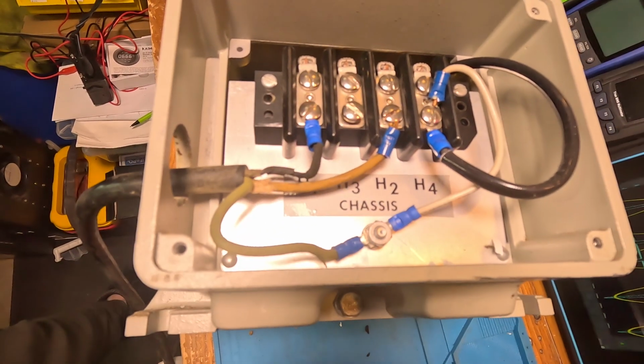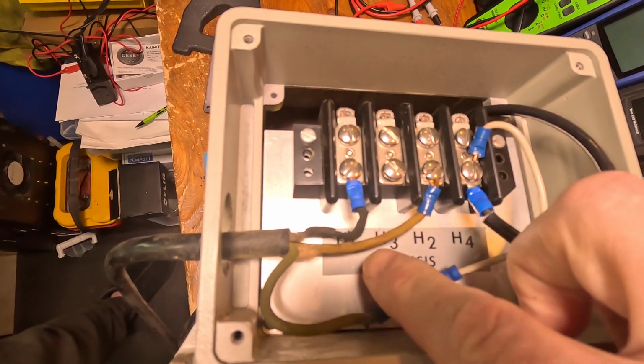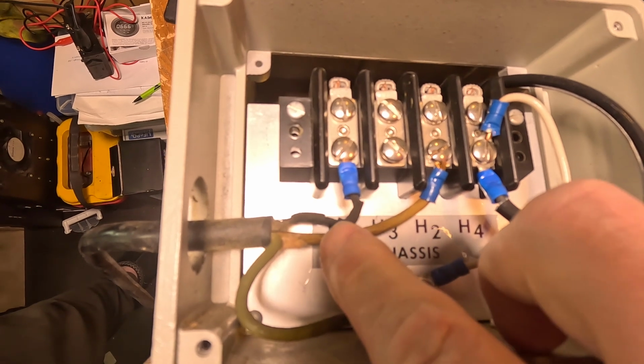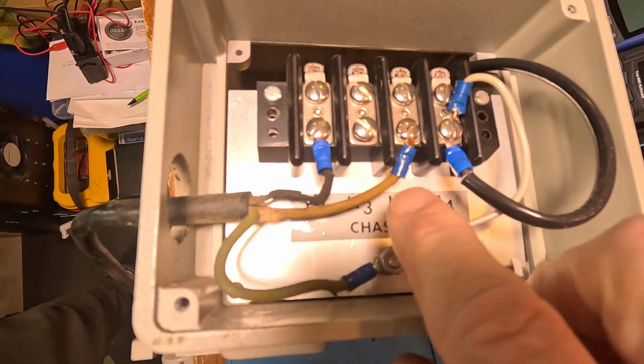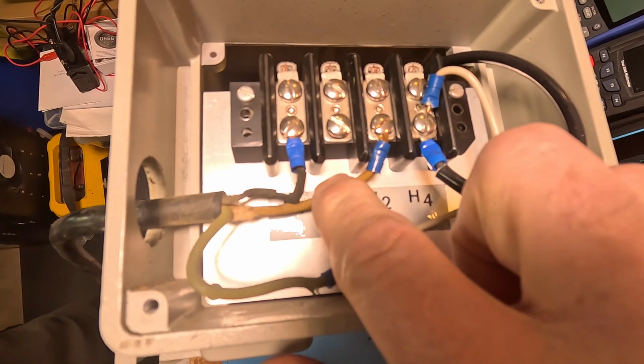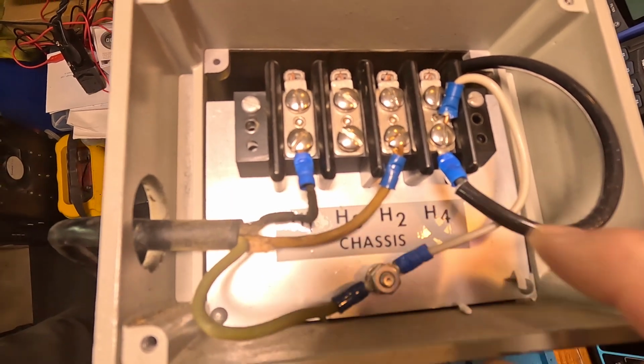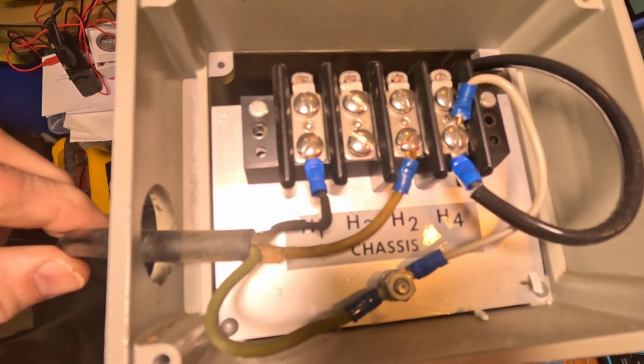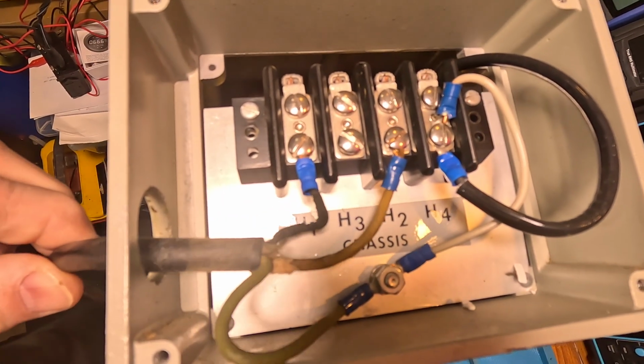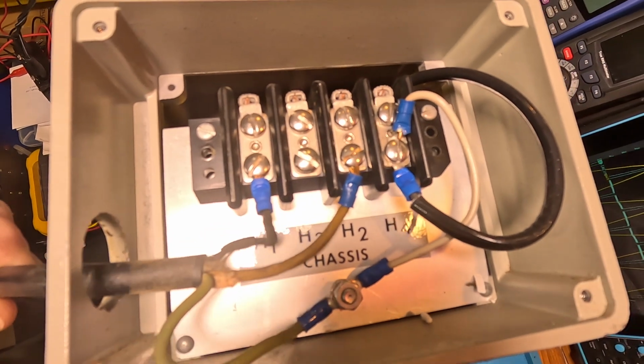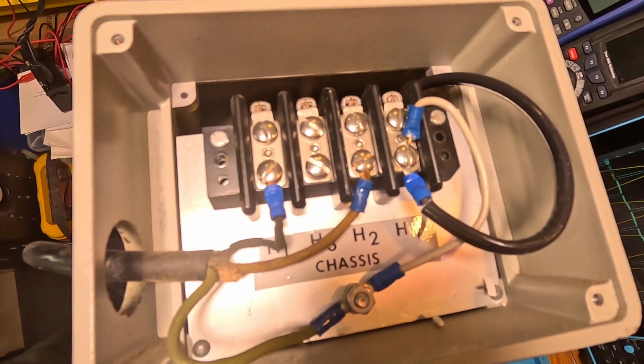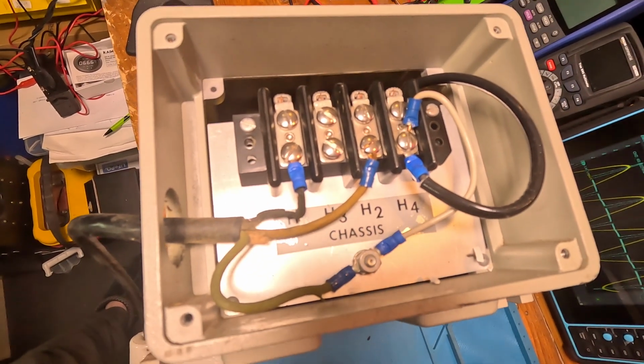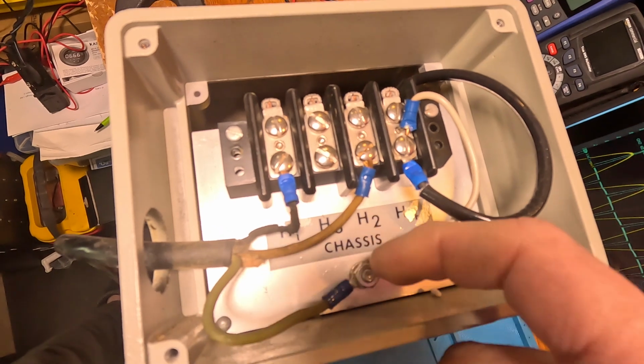The concern's growing. On this side, same thing, the insulation on the black one's all charred and flaking off. Terminals all look great, this white wire looks good, but the way this was put in, you could just pull and stretch it, which is not good. That's not a good installation.